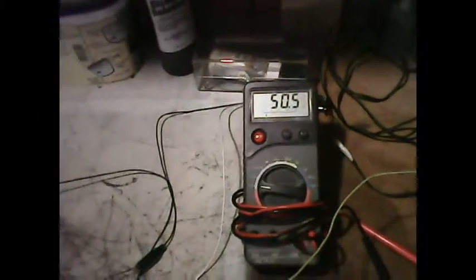So now I'm at 50 volts across the motor. Again I'm going to check the voltage here, and it should be close to the same value. I put it down here again, and I'm getting around 50 some volts - that's tracking at this range. When I touch the positive here, 62 volts - that's the 62 volt range. So I have 50 volts coming out there, meaning I want about a 10 volt drop between the motor and the supply voltage at all times. So the motor is tracking about 10 volts lower than the supply voltage on both ranges.